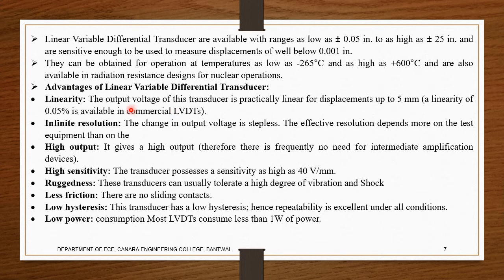Now, the advantages of LVDT. First is linearity. The output voltage of the transducer is practically linear for displacement up to 5 mm. That is a linearity of about 0.05% in commercial LVDTs. Second, infinite resolution. The change in the output voltage is stepless. The effective resolution depends more on the test equipment.